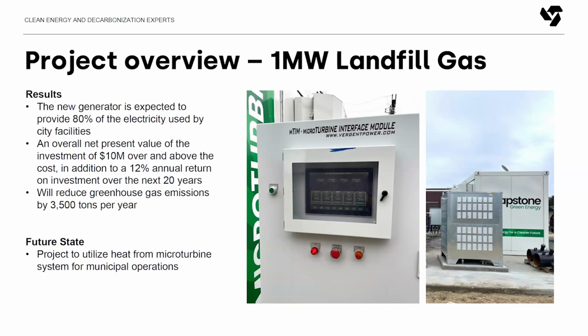Because the microturbines have all their thermal energy in the exhaust, and there's no oil or water jacket or anything like that, it's very easy to incorporate heat recovery later. We can add heat recovery on a single C200 bay at a time and incorporate it back into heating the local facilities on the landfill site, or we can common duct the exhaust together into a single stream and recover the heat to put back into the building.